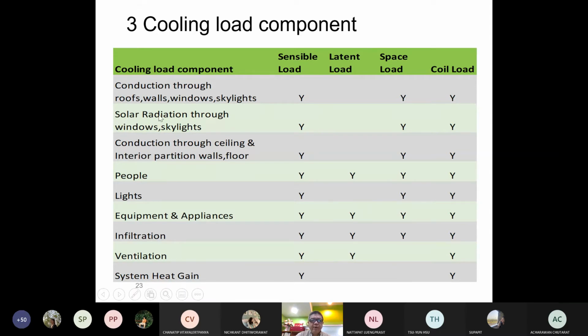Second is solar radiation through the windows and skylight - this is also sensible load, creating temperature rise. Then conduction through the ceiling, interior partitions, walls and floors - this is also sensible load. But when you look at people, they have not only sensible but also latent heat, because when breathing or sweating there is humidity, so they have both sensible and latent load. The light is only sensible load. Equipment and appliances can also be both sensible and latent.